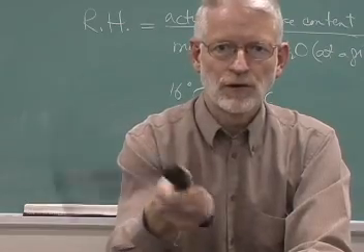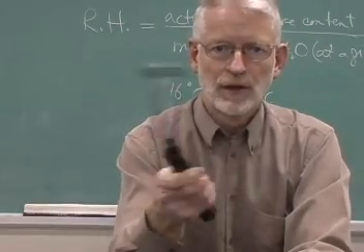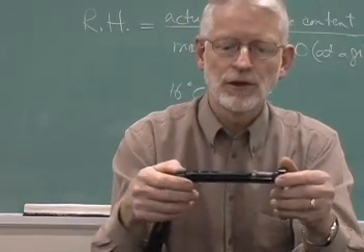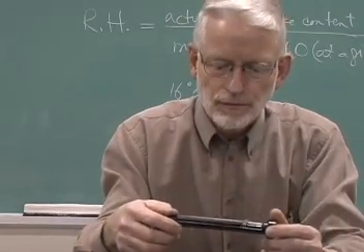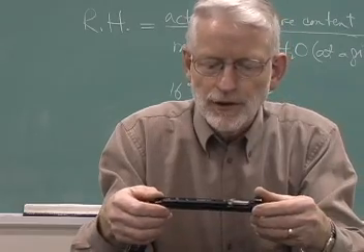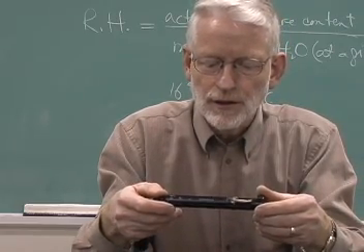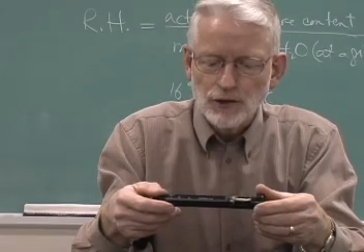We do this for about a minute or so, and then we stop it and we record then the two temperatures. My wet bulb in this case is about 16 degrees, the dry bulb is 23.